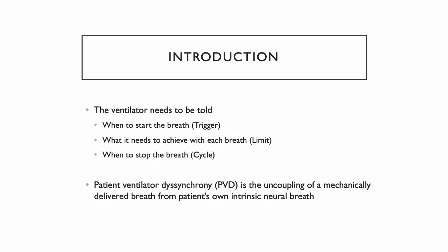The modern ventilator needs to be told when to start the breath, which is known as the trigger, what it needs to achieve with each breath, known as the limit, and when to stop the breath, which is known as the cycle.